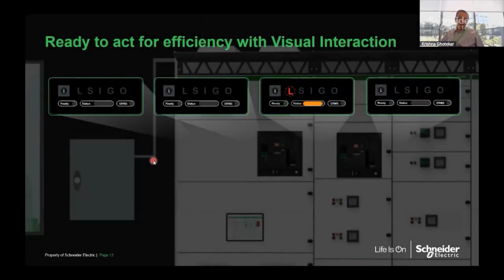In terms of trip unit, these are the different scenarios. One of the scenarios is, let's say the breaker is off, all the LEDs are off, as long as we have not supplied a 24-volt DC power supply. Second option is the breaker is in on condition, so the ready LED will be blinking, indicating that the breaker is ready for protection or a next operation.